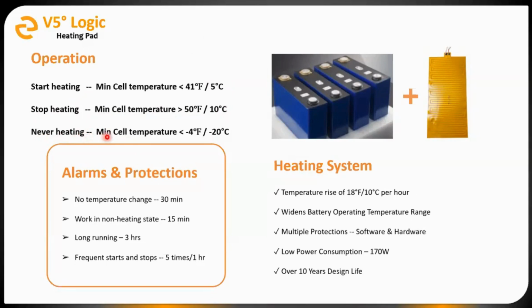The low end limitation of the heating pad is minus 4 Fahrenheit or minus 20 C. That's getting into the operational limitations of the battery itself. Below these temperatures, the heating pad unfortunately is not operating.